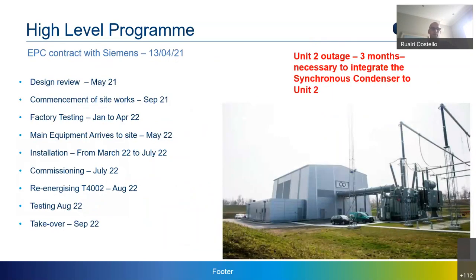High-level program design review started last year, in 2021. Siemens started on site in September. Factory acceptance testing has just been completed recently, in April. The main equipment, the motor and flywheel, will arrive from May, but we do have some small transformers coming next week. They're on site doing installation works at the moment. Between March and hopefully July, that has to be completed so as to re-energize the shared transformer. Commissioning is in July and testing in August, with final takeover in September.